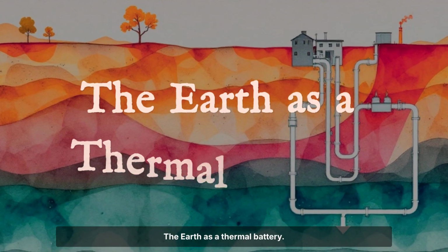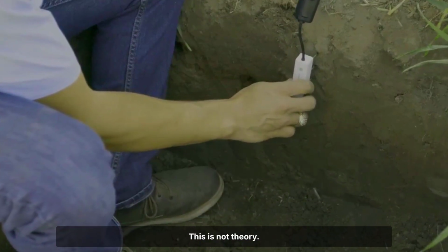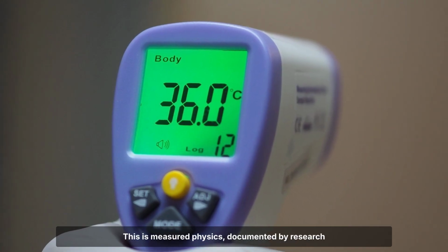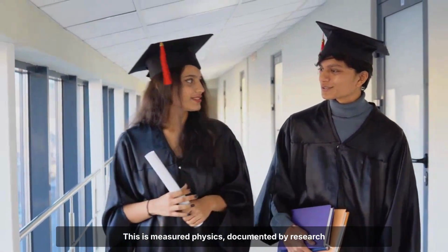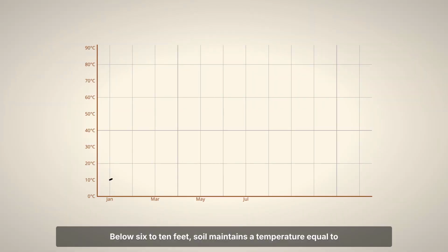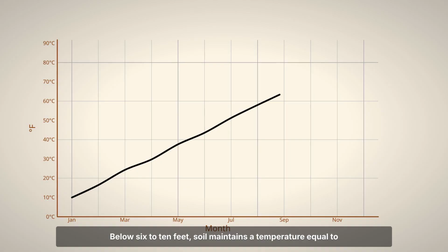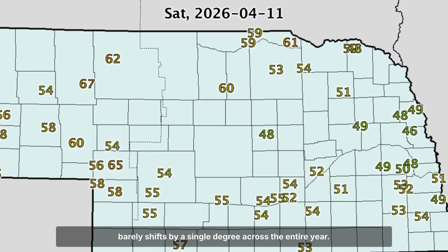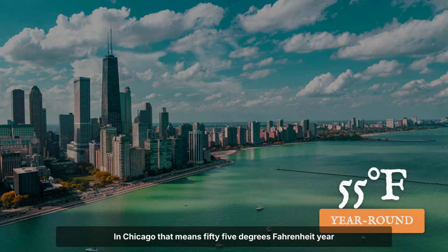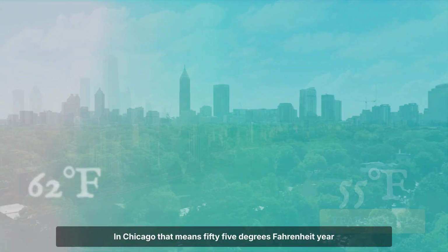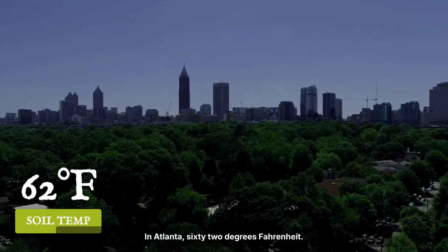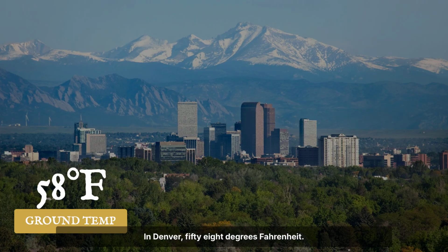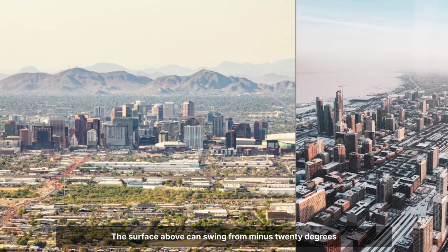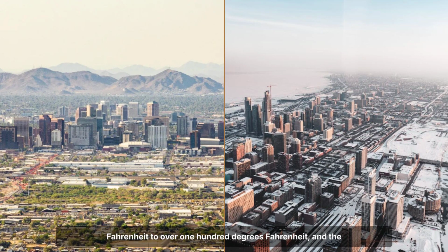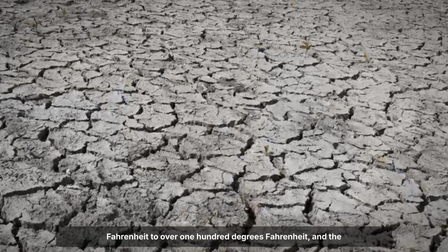The Earth as a thermal battery. This is not theory. This is measured physics, documented by research institutions worldwide. Below 6 to 10 feet, soil maintains a temperature equal to the annual mean air temperature of that region, and it barely shifts by a single degree across the entire year. In Chicago, that means 55 degrees Fahrenheit year-round. In Atlanta, 62 degrees Fahrenheit. In Denver, 58 degrees Fahrenheit.